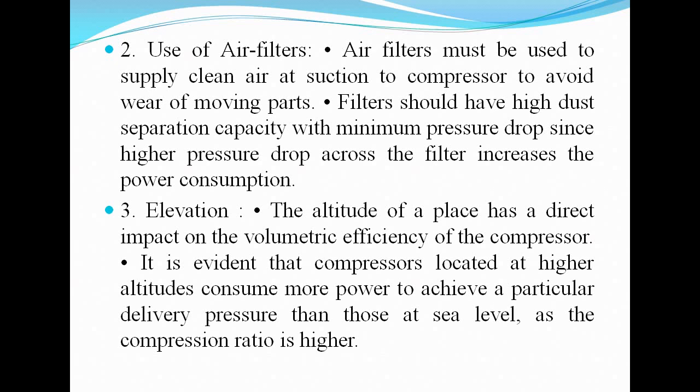Third, elevation. The altitude of a place has a direct impact on the volumetric efficiency of the compressor. It is evident that compressors located at higher altitudes consume more power to achieve a particular delivery pressure than those at sea level, as the compression ratio is higher.